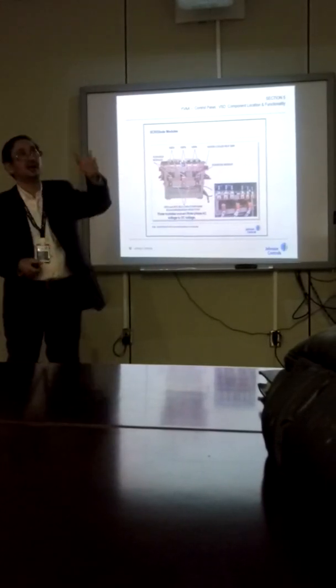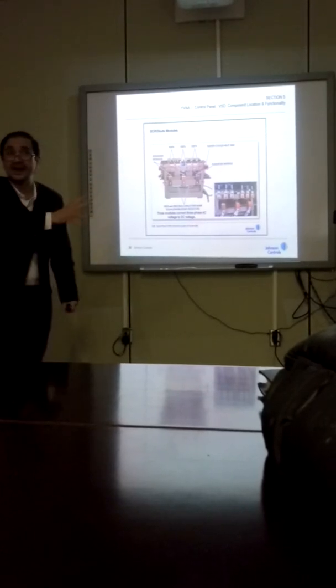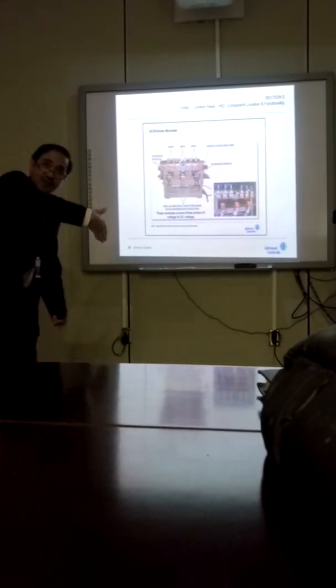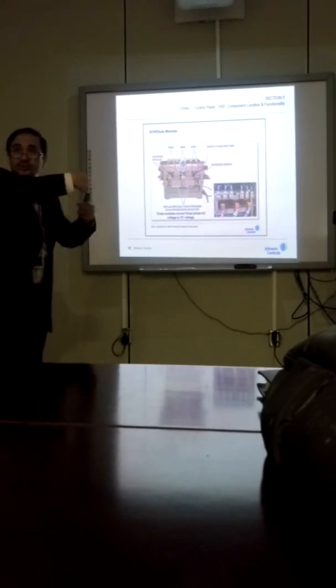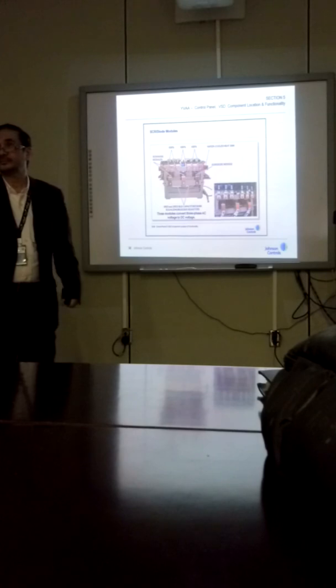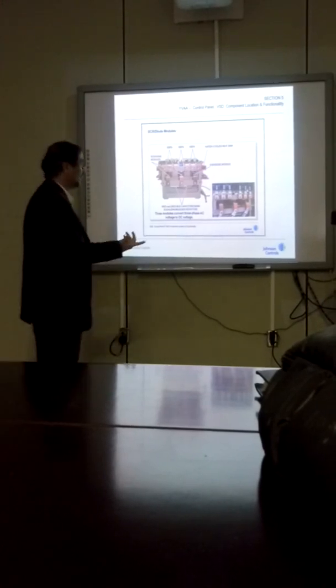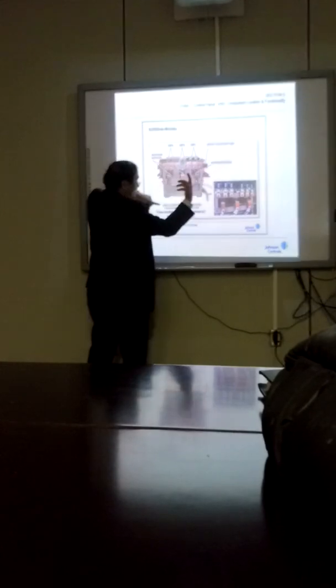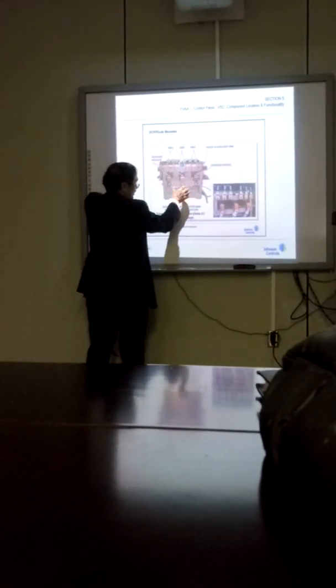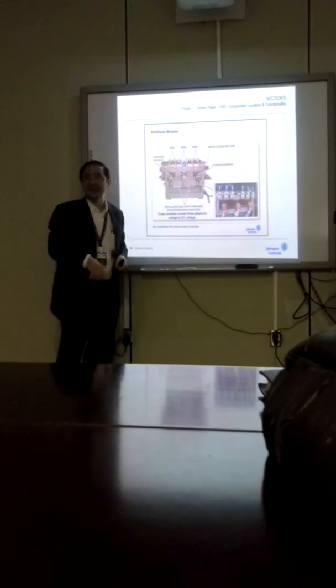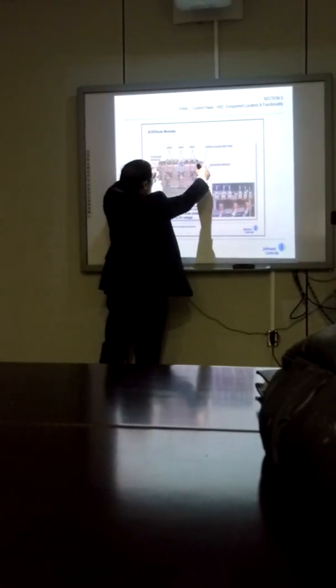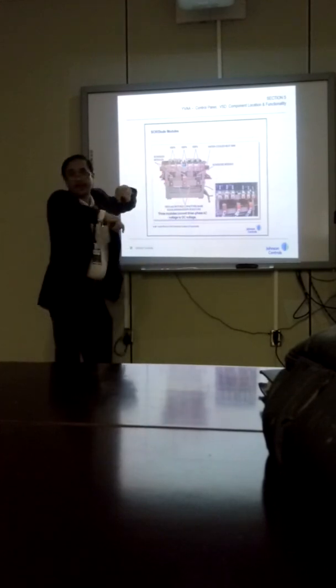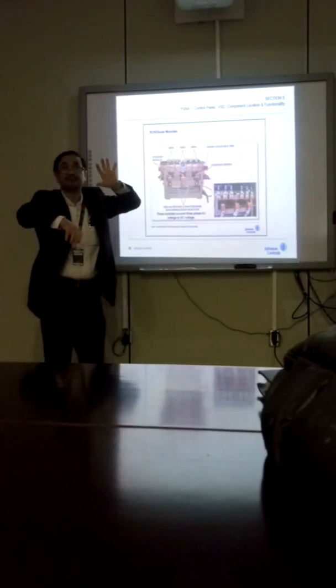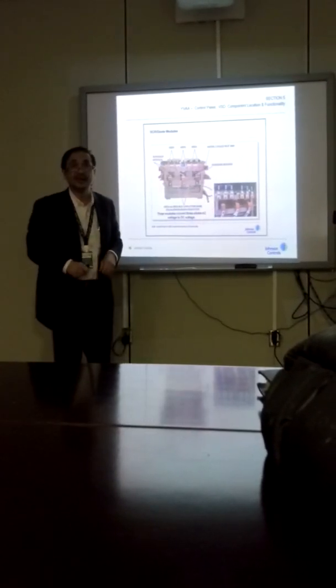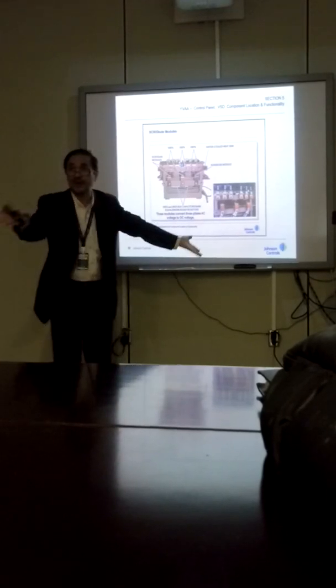If you notice on the panel, there's a warning sign. Warning. After shutdown, wait 15 minutes before you open. Right? If you read the sign, operations. The reason why it needs 15 minutes is to bleed off and drain the power on this bank of capacitors. Okay? After 15 minutes, the power here should be 0 volt DC. Where does it go when it is shut off, no power?